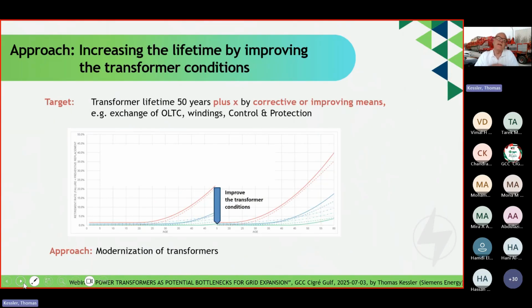The next step is also increasing the lifetime of an aged transformer by improving the transformer conditions. If a transformer has already reached, let's say, the last third of the bathtub curve, then through certain defined transformer service actions and service measures, we can improve the transformer conditions - we can rejuvenate the transformer. To a certain degree, in this case we can stretch the bathtub curve and expand the transformer lifetime.